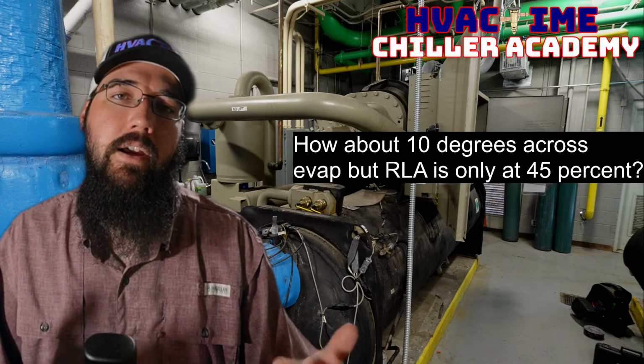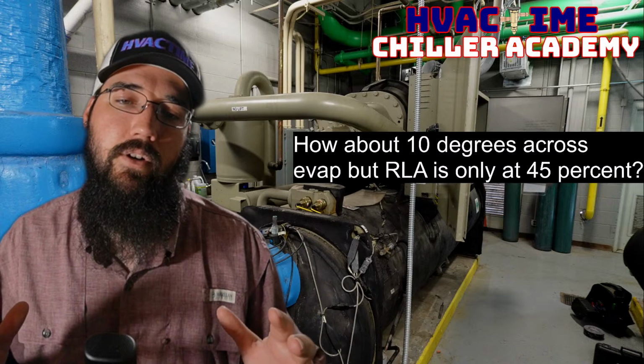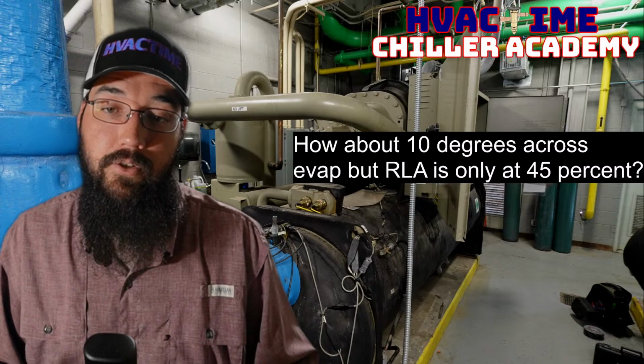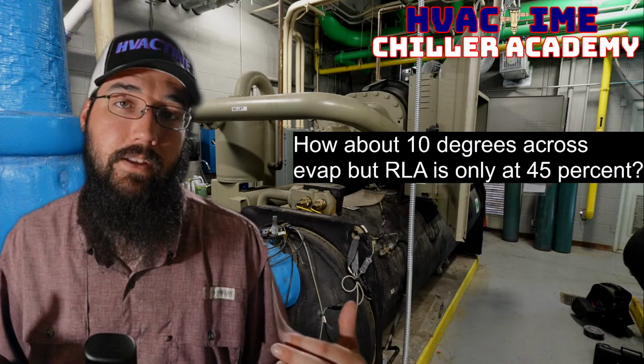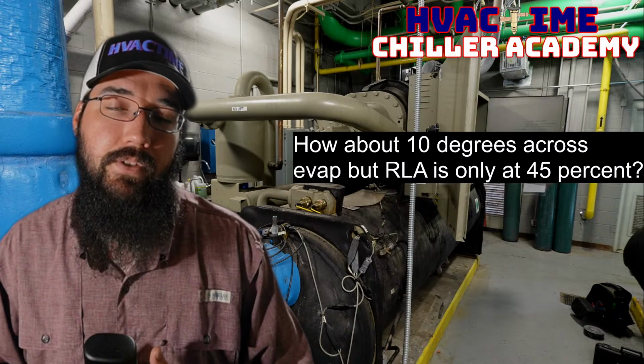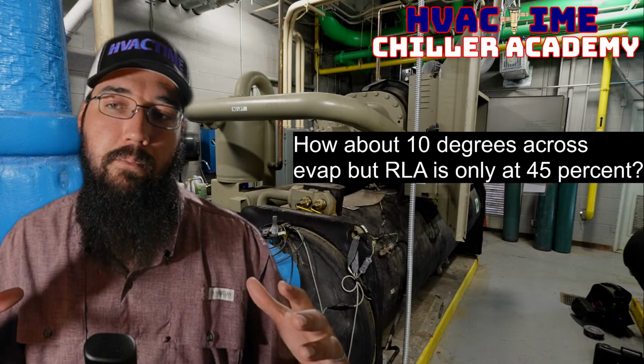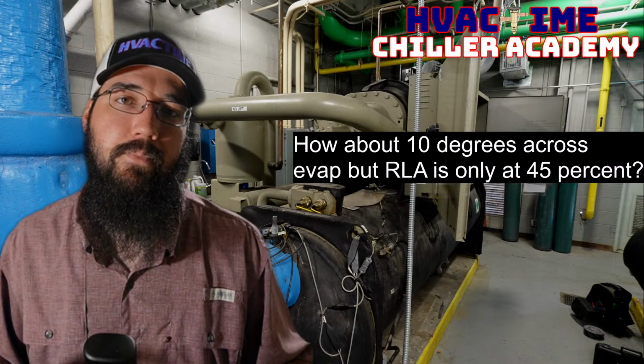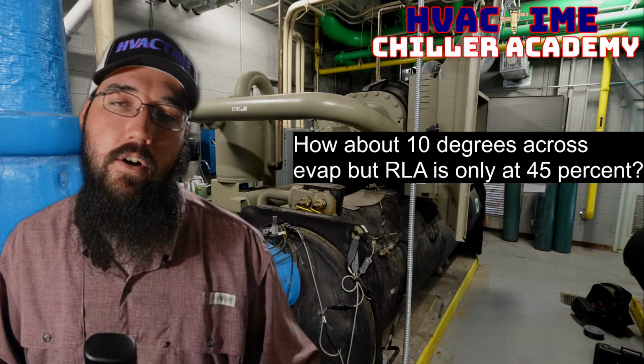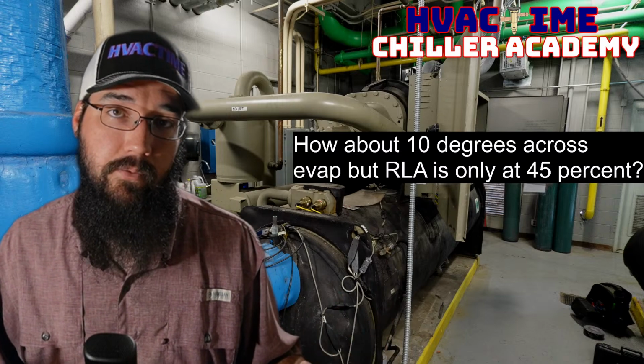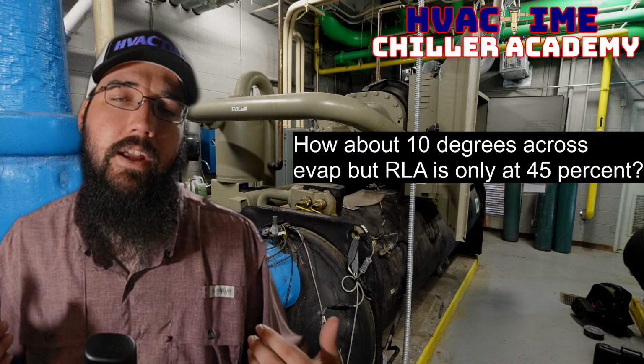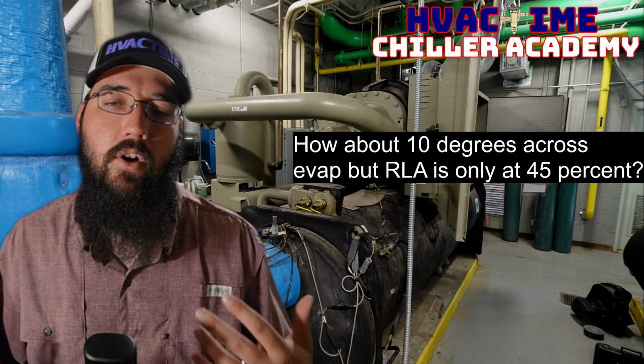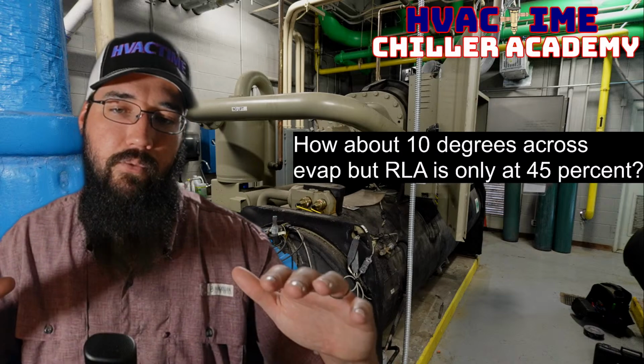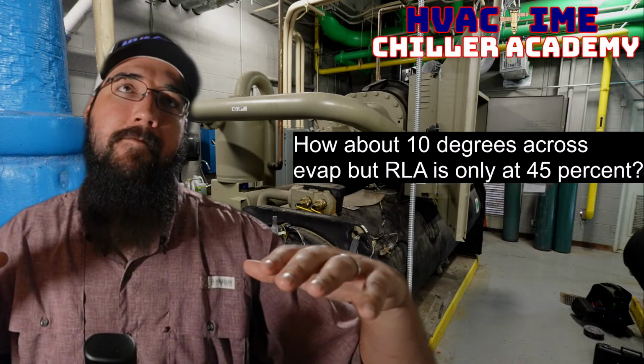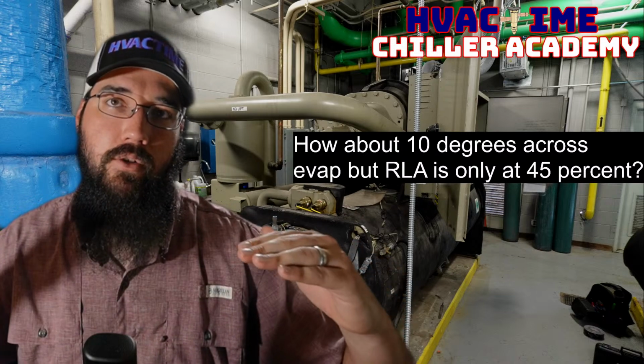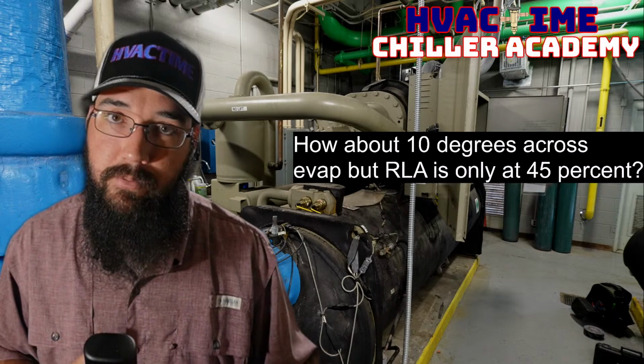So yeah, that would be my assessment if I had a condition that I would consider fairly loaded, a 10 degree and everything's correct in terms of design specs, but I've only got a 45%. I would say that we've got a full load, but we're managing our lift really, really well. And that is enabling a really low RLA, which is where you're maximizing the coefficient of performance, the COP. We've got a really good COP at that point, which is all part of why, in a water cooled environment, if we can get that head pressure down and keep our condenser water under control, we can save a huge amount of efficiency.